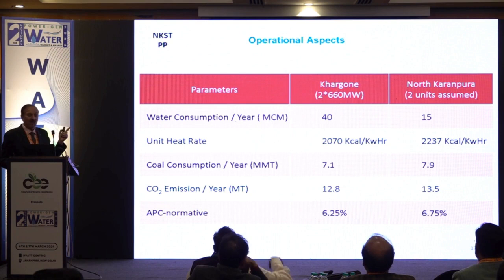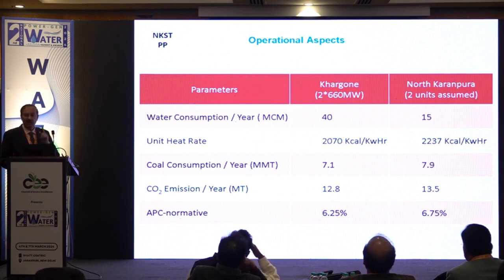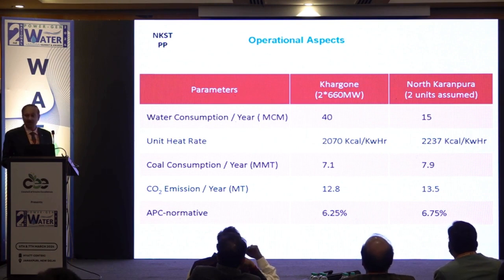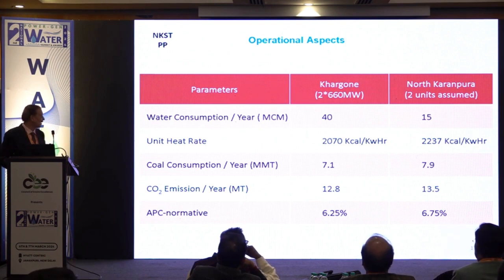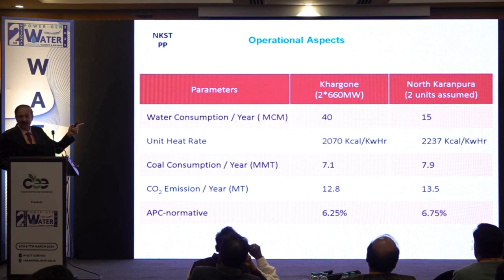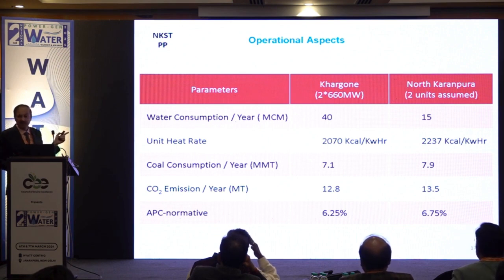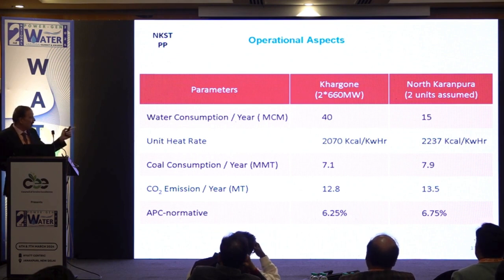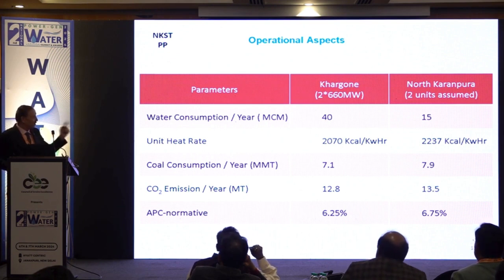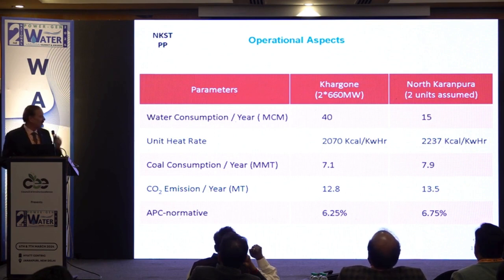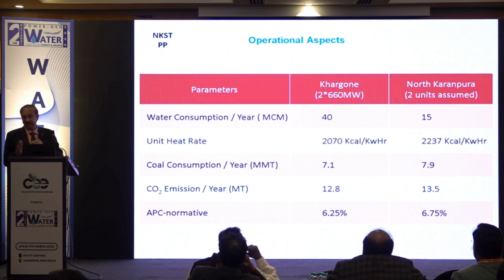So NTPC Khargone is having 2 units of 660 megawatt with a conventional water-cooled condenser, and North Karanpura is having 2 air-cooled condensers. So water consumption, you will see there is a drastic difference from 40 MCM, it will drop to only 15 MCM at North Karanpura. Unit heat rate, as I said earlier, will go up significantly. At Khargone it is 2070, at North Karanpura it is 2237. So it is a give and take.